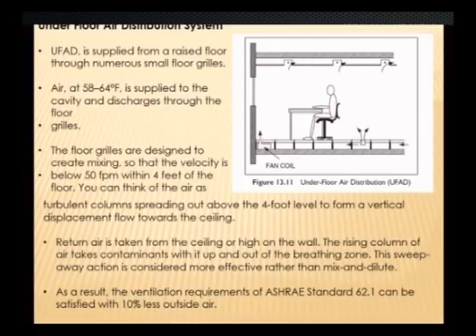The rising column of air takes contaminants with it, up and out of the breathing zone. Because of this displacement, the rising air picks up all these contaminants and moves them above the breathing zone. This sweep away action is considered more effective than mix and dilute. As a result, the ventilation requirements of ASHRAE standard 62.1 can be satisfied with 10% less outside air.